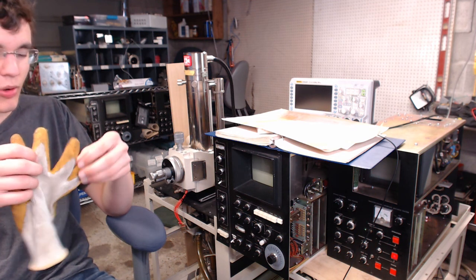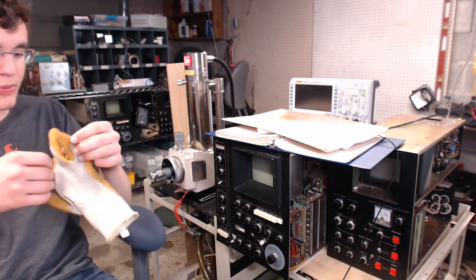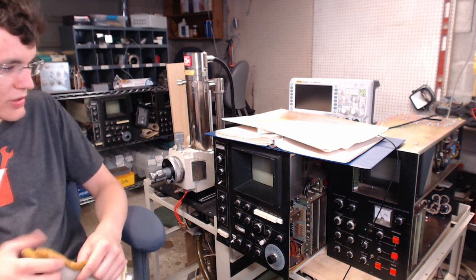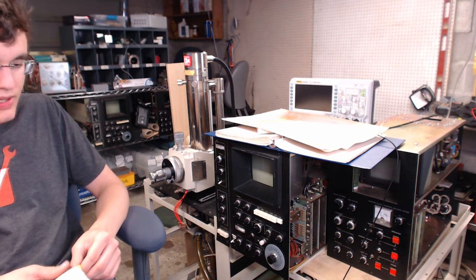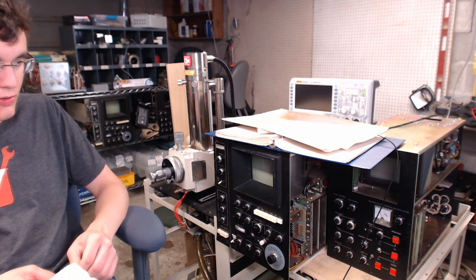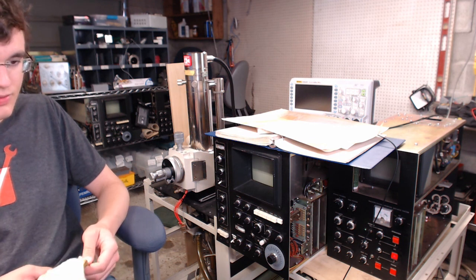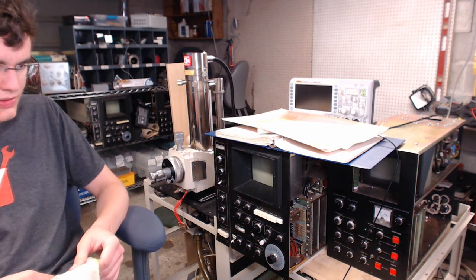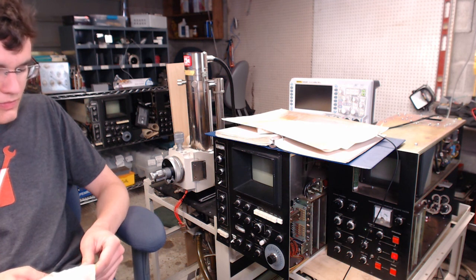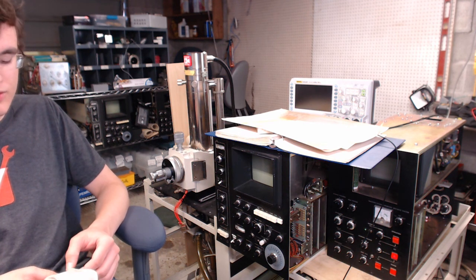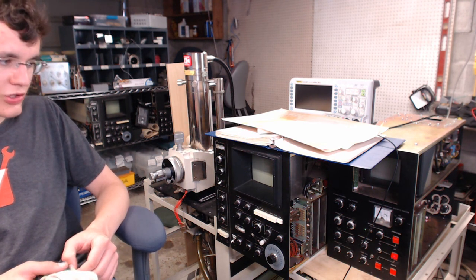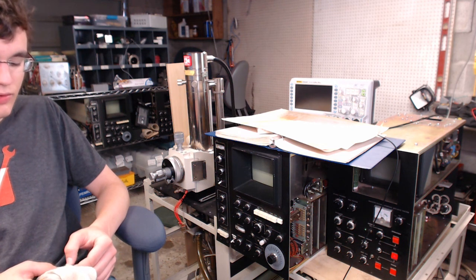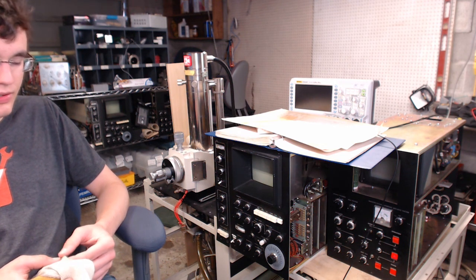So, well, I mean, I know what it means. It means the point on the scale, I just don't know what pressure it correlates to. And there's not really a convenient spot to put another vacuum gauge on. So I'd have to kind of machine an adapter to do that. I don't really want to do that. And I can't just replace the current gauge because the current gauge is tied into the logic circuitry in the SEM. So a lot of stuff will automatically shut off if it doesn't detect any signal on the gauge.